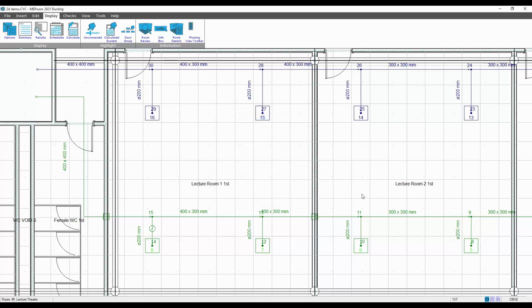Obviously manufacturers have volume control dampers on their grill, so if you have a short run you may not have a damper. You would merely apply that to the grill when placing it, so you would add that extra resistance at this point here. So we've already applied 15, so you would apply the addition to the 15 pascals to balance the system.